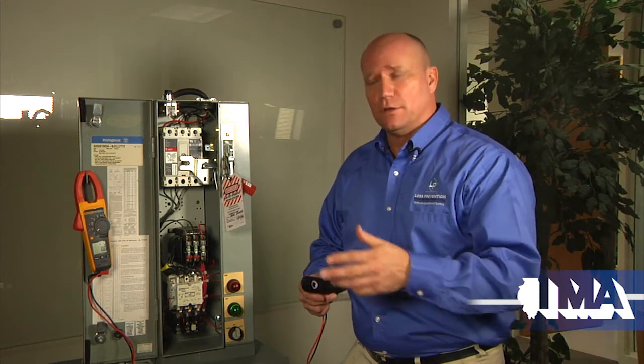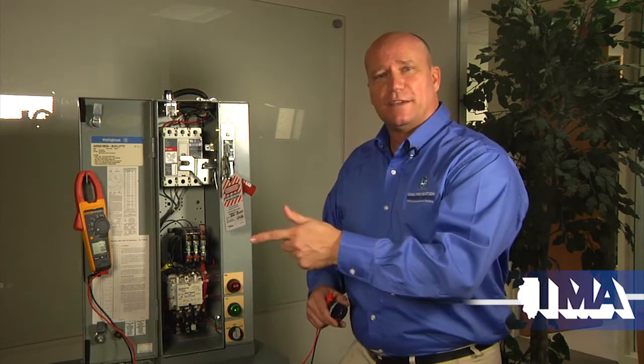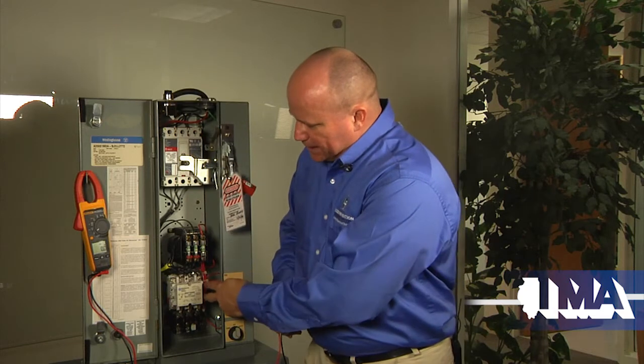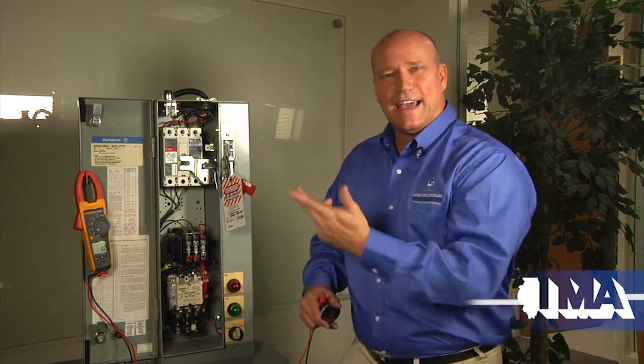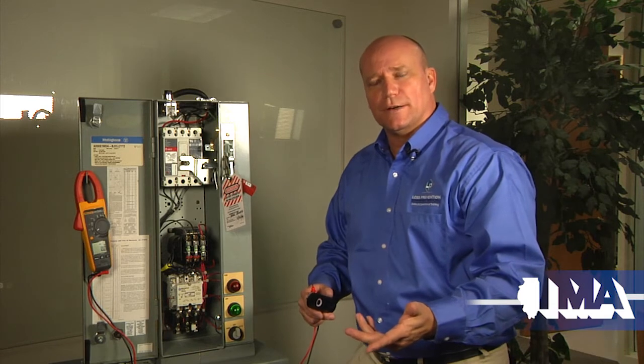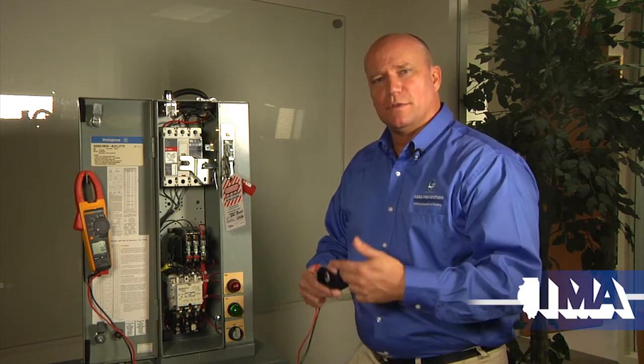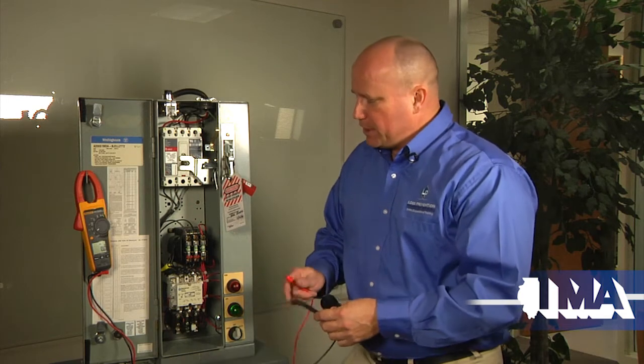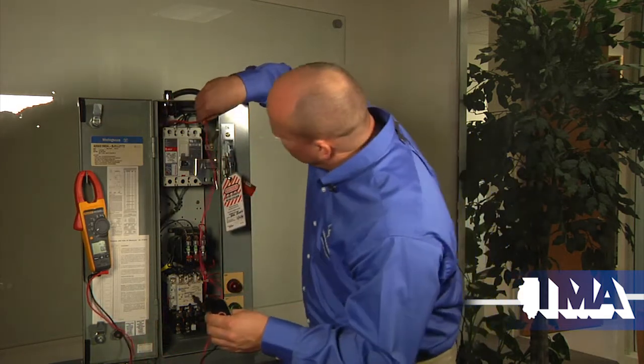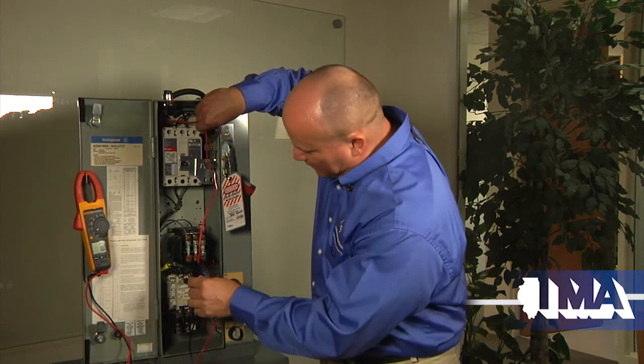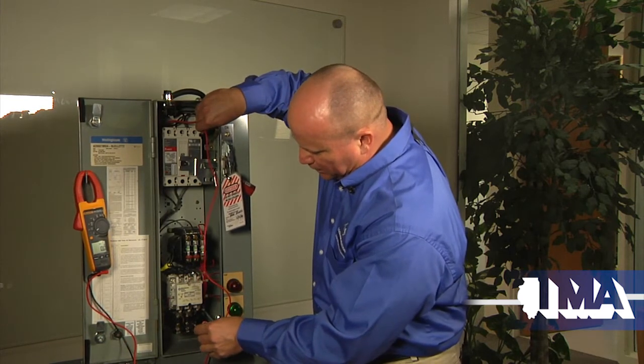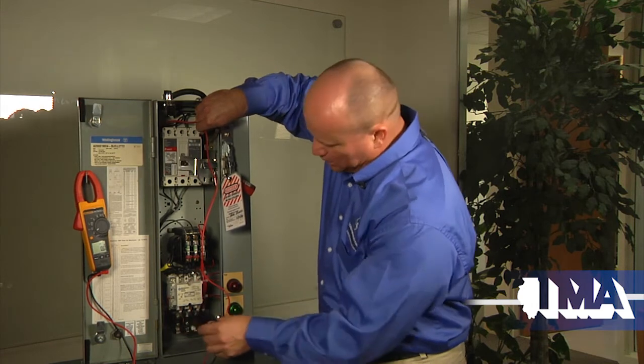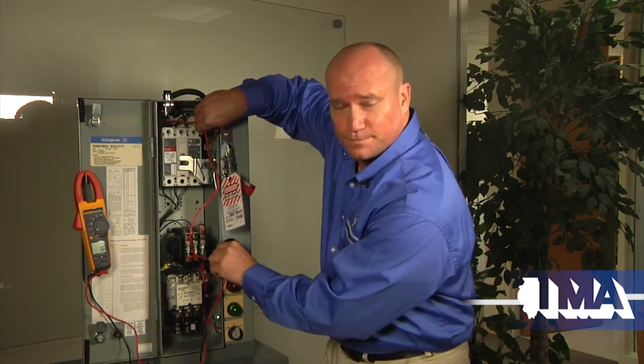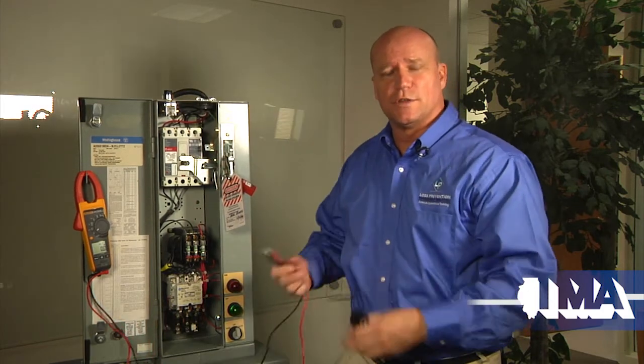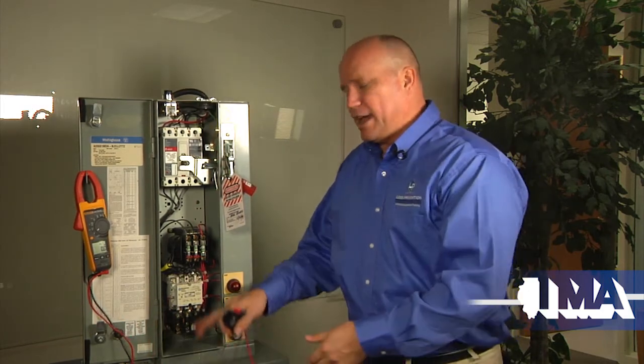For example, remote indicating power to indicate that the motor is running or stopped has to have power coming from an external source to an auxiliary contact on this main contactor and then back out. So you're going to have another potential voltage source there. You have to know that about the equipment before you start working on it. A good thing to do is to leave a lead on ground and then check every potential point, including potential backfeed from the motor and the auxiliary contacts, to make sure that there are no other sources of power coming in. Why off the motor coming back to the controller?